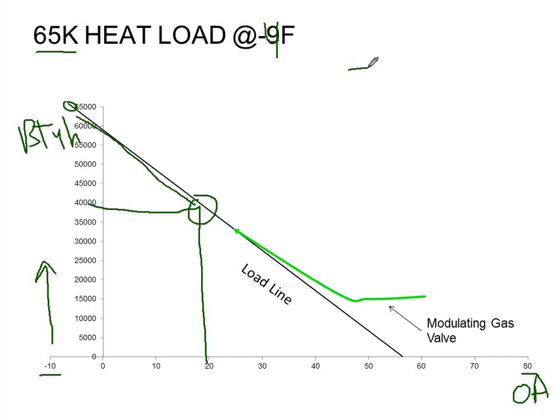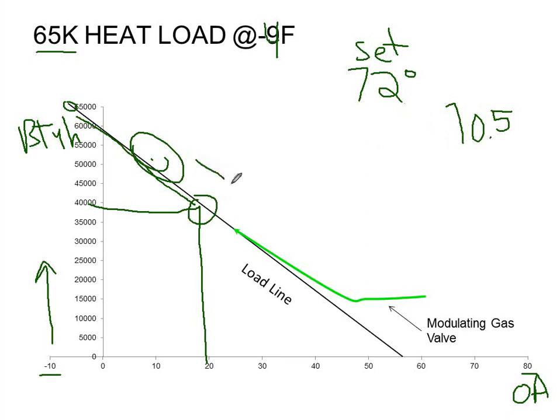So what does that mean? That means if your set point is set for 72 degrees on your thermostat or on your Evolution Infinity controller, we look to see are we above or below that with the actual temperature. So if that's our set point and our actual temperature is, let's say, 70.5, great. I'm 1.5 degrees off. I need a lot of capacity. I'm going to be ramping up here on the high end of my burner capacity. But then as I get closer to 72, I get to 71, I modulate back a little bit. I get to 71.5, 71.7, 71.8, 71.9, 72 even. I still got my burner on, whereas a normal thermostat would have shut him off. My burner's still on, but it's at a really small flame, a very low firing rate. And then if I get above 72 degrees, then I'll start backing him off a little bit, right? Back him off, until eventually maybe I will shut him off completely.